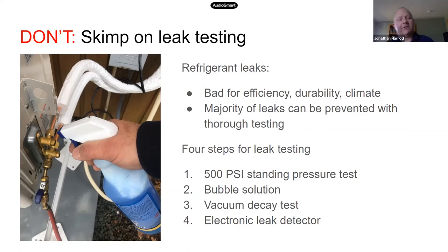Once we actually put the refrigerant into the system, we go back and do one more test. There are a few points in the system that you can't test with these other methods, like the actual valves that you connect to the system. So we'll go through at the end with an electronic leak detector and pass a little wand over these spots, and just make sure that there are no leaks at all.